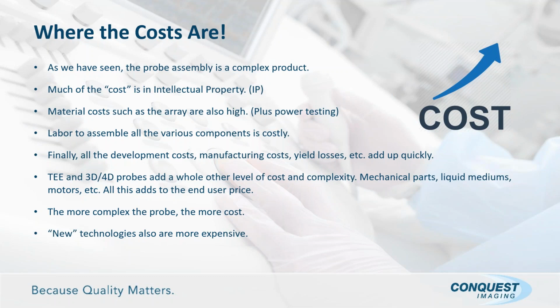As soon as you start getting into TEE, 3D, 4D probes, that just adds a whole other level of complexity. You've got mechanical parts, you've got liquid mediums, motors, drive cables, things like that. That all adds not only to the design cost, but also the manufacturing costs of these. And the bottom line is the more complex the probe is, the more it's going to cost us. And these new technologies do tend to be more expensive. And again, let's face it, there's a market value that the manufacturers try to put on probes and other devices. How they calculate that varies, but I do know when someone rolls out a new technology, they're going to try to get top dollar for it. But there is a cost behind it to an extent as well.